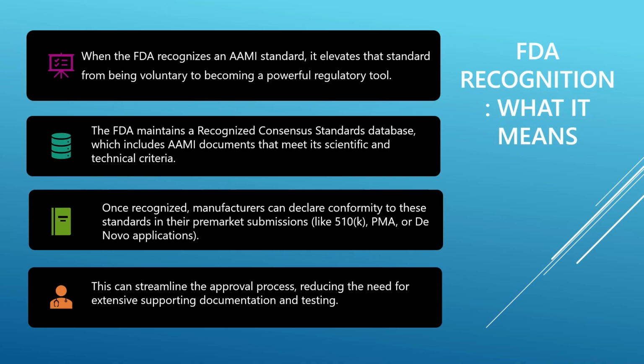AAMI standards gain even greater significance when formally recognized by the FDA. Remember, the FDA can only recognize standards, not TIRs. So what happens when the FDA adopts an AAMI standard? When the FDA recognizes an AAMI standard, it's no longer just a helpful guideline. It becomes a regulatory tool. It's added to the FDA's recognized consensus standards database, which is a key resource for manufacturers and regulators.